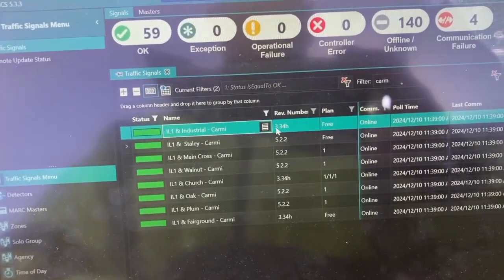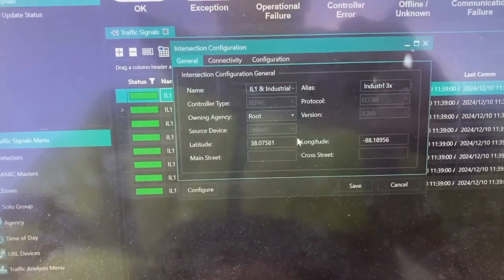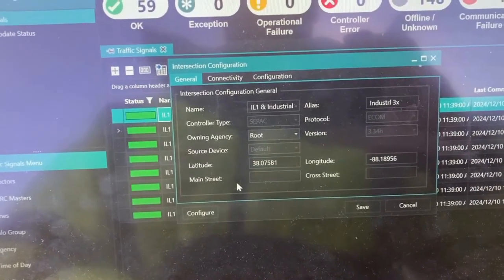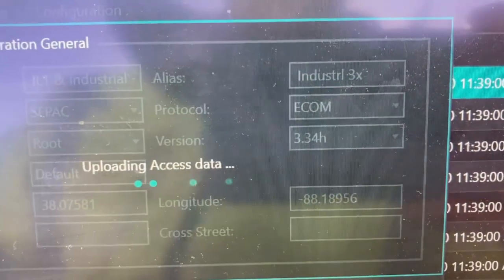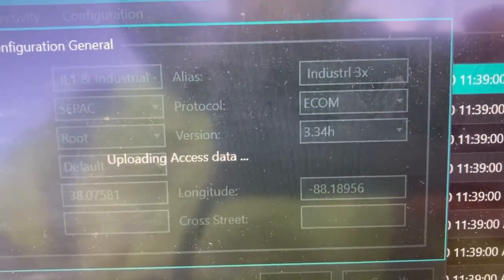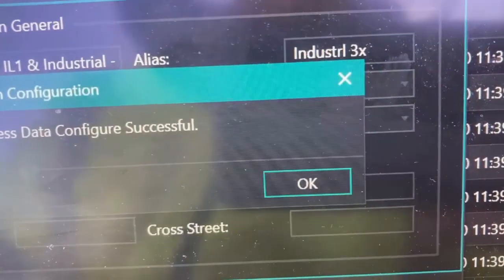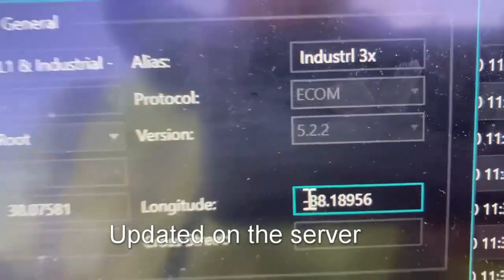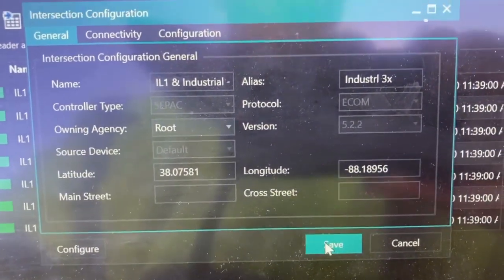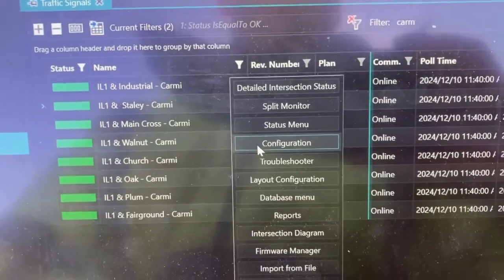Let's go to configuration — right now it's set for 334, so let's configure it to go to 522. Uploading access data. I'm remotely connecting to it, let's see if that changes to 522 for software version. Successful — let's OK that. There it is, it's updated. We can save that now. That's awesome that we connected right away; I know we're right in there talking to the actual controller.